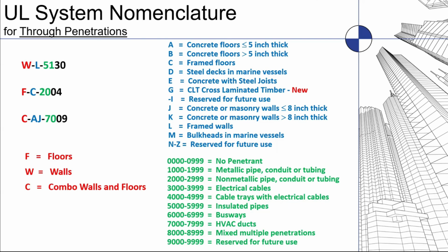So in this case, this is a penetration type of listing, and there are indicators of what it's used in. For instance, the red lettering, WFC, stands for wall, floor, or a combination of floor or wall - it's an indicator of the orientation of the item being tested. The second set of letters, LCAJ, tells you what it's made of. So in the blue lettering, L is a framed wall, C is a framed floor, and AJ would be a concrete floor or masonry wall - could be a combination of certain thicknesses.